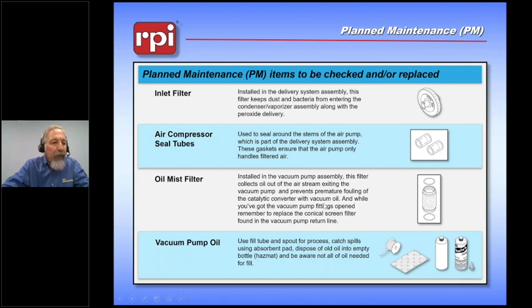Within the PM kit, we have an oil mist filter. These vacuum pumps that are used in hydrogen peroxide sterilizers will generate an oil mist along with the outflowing air. We need to condense that mist and return it back to the pump so it can use it as oil. We give you the amount of vacuum pump oil that you will need. We give a way to manipulate the oil and an empty bottle so that you can take the oil that's been used within the system and treat it properly.